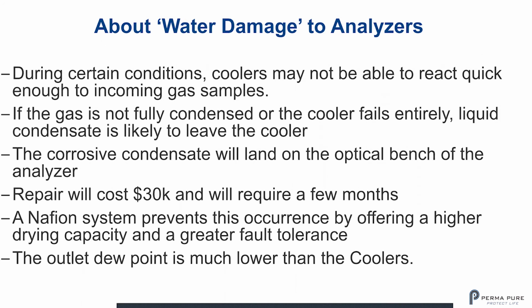So let's look at water damage to analyzers. During certain conditions, coolers may not be able to react quick enough to incoming gas samples. If the gas is not fully condensed or the cooler fails entirely, liquid condensate is likely to leave the cooler. The corrosive condensate will land on the optical bench of the analyzer. Repair will cost $30K and will require a few months. A Nafion system prevents this occurrence by offering a higher drying capacity and a greater fault tolerance. And the outlet dew point is much lower than coolers, as I mentioned before.